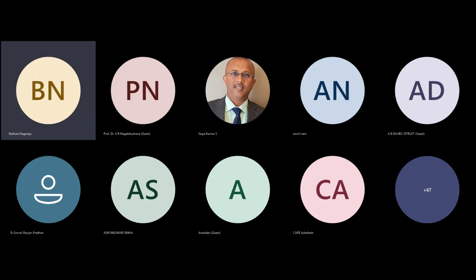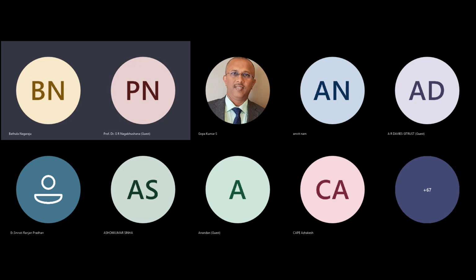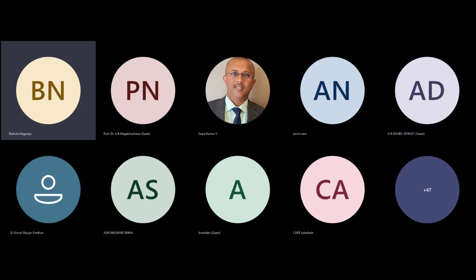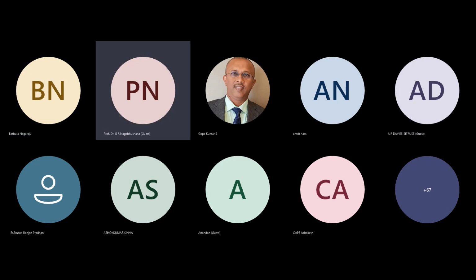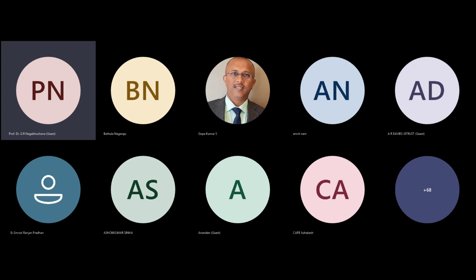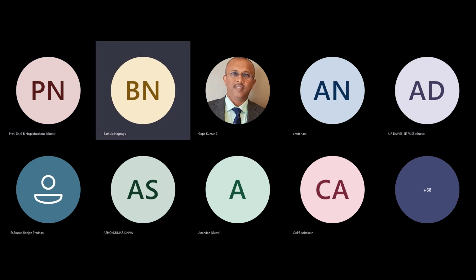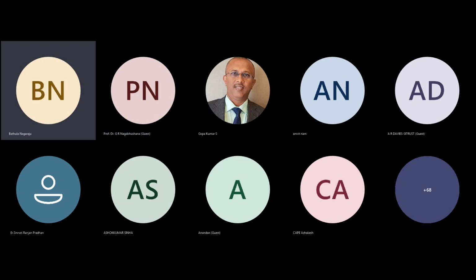And one more thing: whether calculating with the rolling sphere method or the protective angle method, in an isolated lightning protection system, the distance between the point of strike and the protected area where the tanks are present, do we consider just the normal rolling sphere or protective angle method, or take any additional care in measuring the separation distance? Okay. Now what you are saying is there's an isolated protection system. The distance between that and the building protected is so much. Is that enough? Yes, sir. With rolling sphere is enough, or any extra care to be taken?